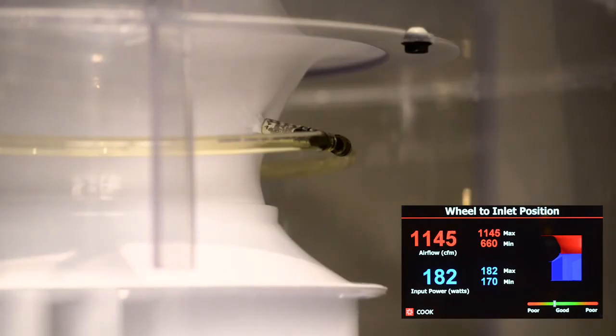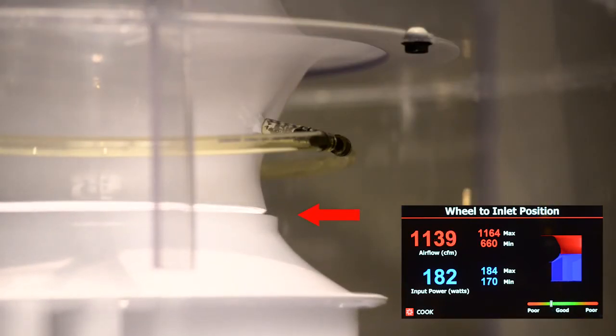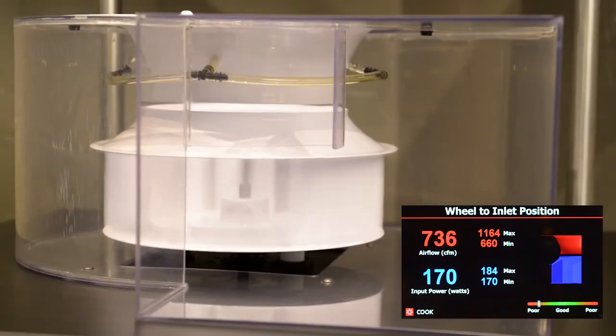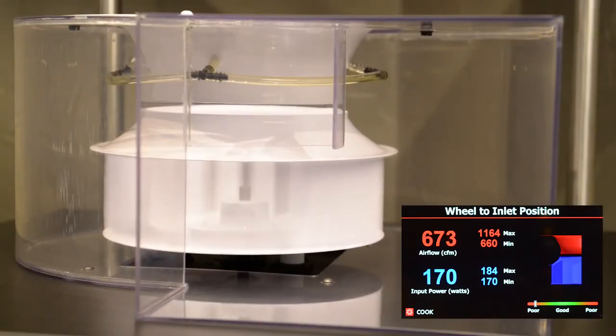Lowering the wheel further, we get to the point where there is no overlap between the wheel and inlet. At this point, some fans may exhibit a whistling sound, as heard here, indicating the wheel is not overlapping the inlet enough.